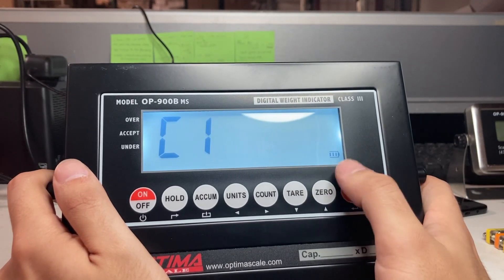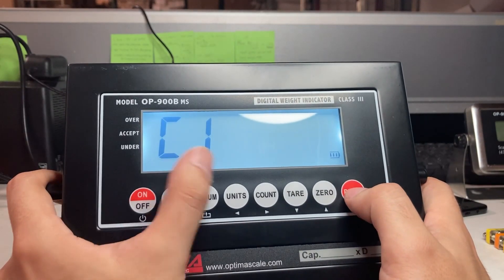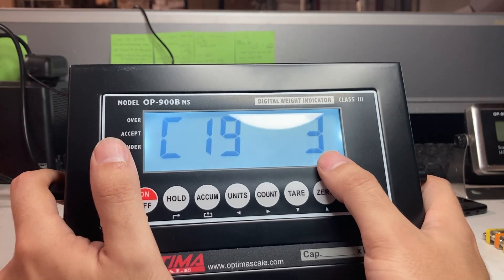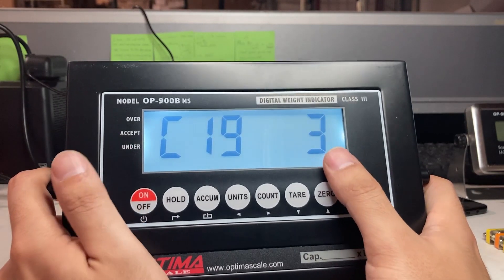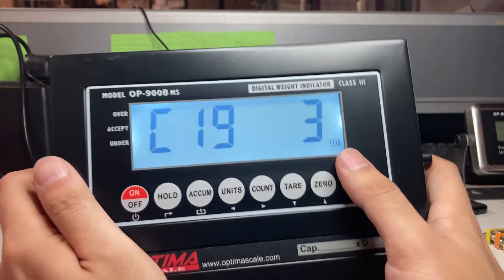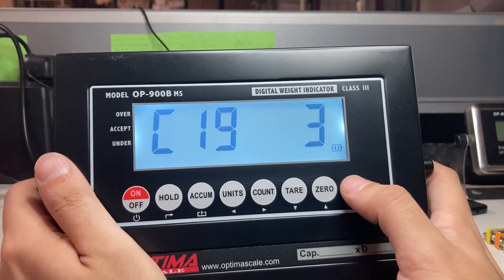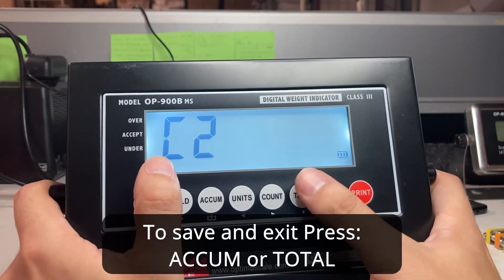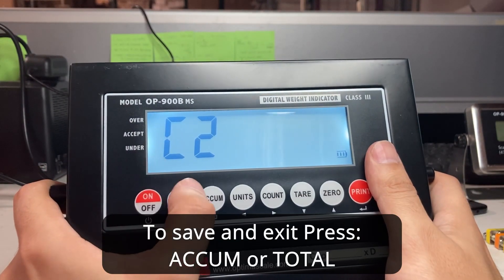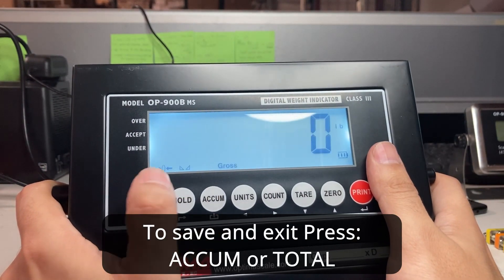We're going to make sure C18 is equal to 3 by pressing the 0 button. This is important for data logging software. C19, this is the baud rate. We're going to set 9600 or 3. Press print. Now the settings are all set up.